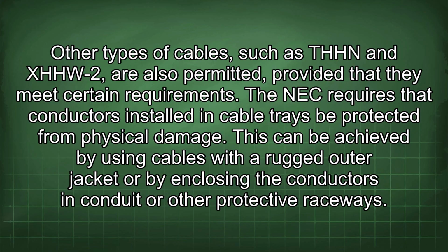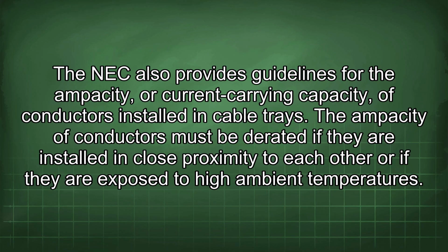This can be achieved by using cables with a rugged outer jacket or by enclosing the conductors in conduit or other protective raceways. The NEC also provides guidelines for the ampacity, or current carrying capacity, of conductors installed in cable trays. The ampacity of conductors must be derated if they are installed in close proximity to each other or if they are exposed to high ambient temperatures.